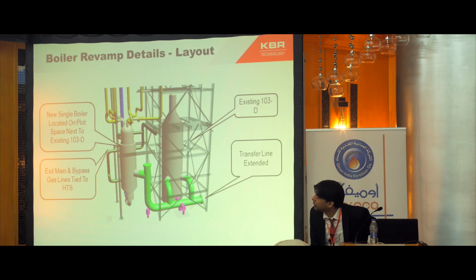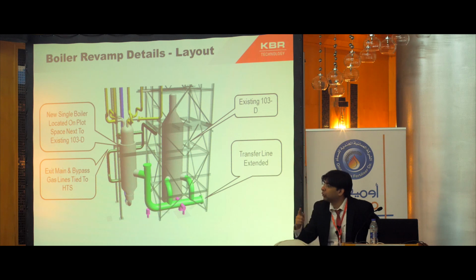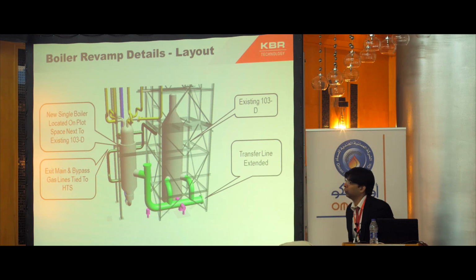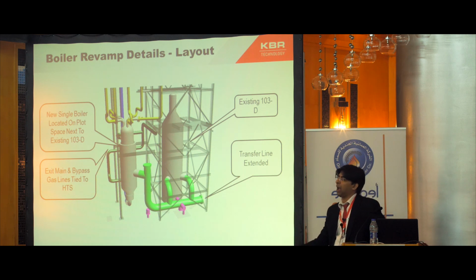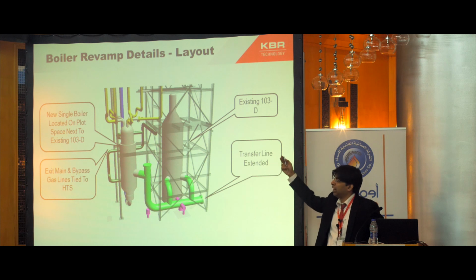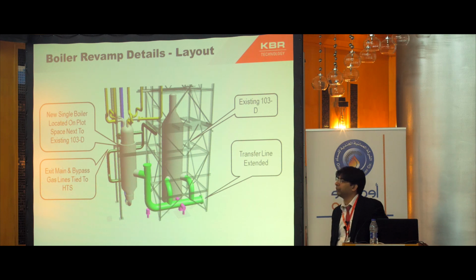Sorry, I have one question. Yeah, sure. The boiler feed water inlet at the bottom, is it directly connected to the pump, or is it coming from? It's coming from the downcomer through the steam drum. Yes, it's a natural thermosiphon boiler. The principle is essentially the same as in the MWK design, but the only difference is earlier it was coming from the top, now it comes from the bottom, though still from the steam drum.